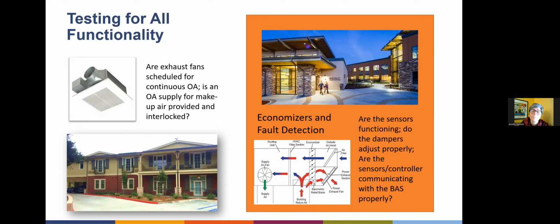A common thing that one of our commissioning agents has seen is that the part of the controls where the economizer connects and talks to the sensors and then to the building automation system is not connected properly. As a result, either the economizer just isn't working at all, or it's always pulling in too much outside air, which is a huge energy waste, or it's not utilizing any of the free cooling, which again is lost energy savings to the owner. So in this building in San Luis Obispo, the commissioning agent caught that early, and they got the economizers connected properly and made sure through the acceptance testing process that everything was working properly.